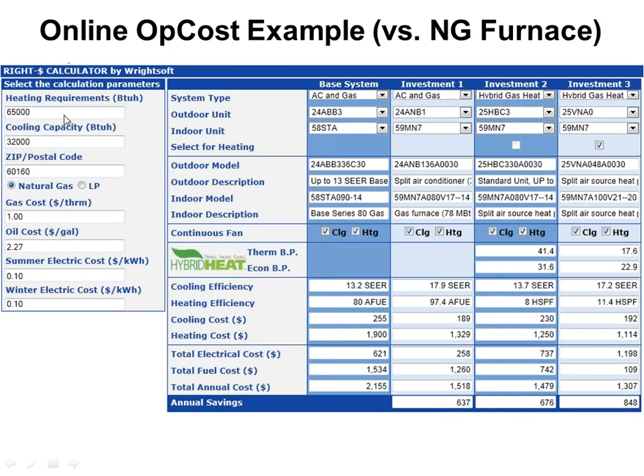Right? But so this is the heating load and the cooling load. You put the zip code so you can get the weather data. You say if you got natural gas or propane. In this case I picked natural gas. At the time I did this screenshot a year ago, I put in $1 a therm. If I were to redo it right now, I'd probably put in 75 cents a therm.